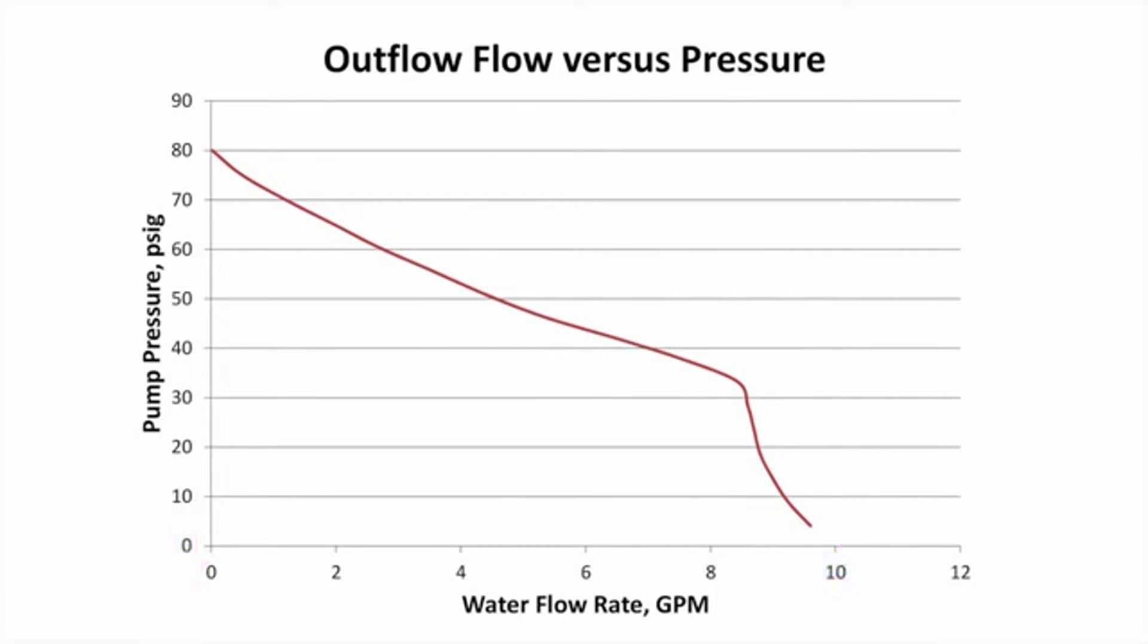The relationship of that pressure to flow is shown by this line. For every pressure, there is only one flow rate that the pump operates at. So in this case, 60 psi would provide a flow of almost 3 gallons per minute.